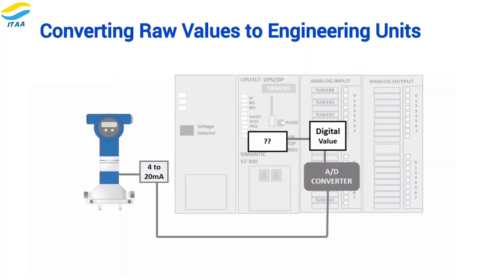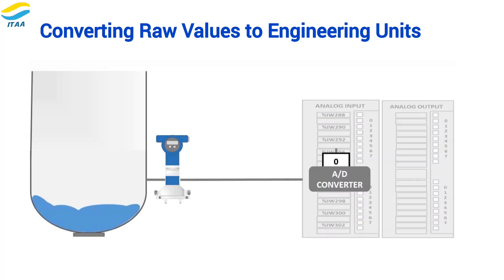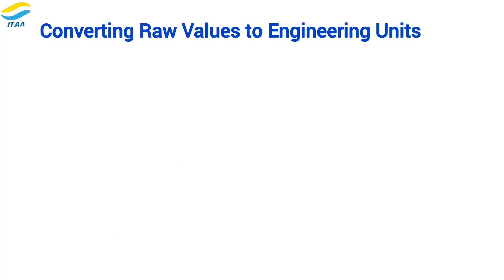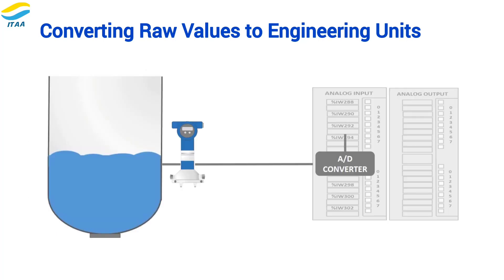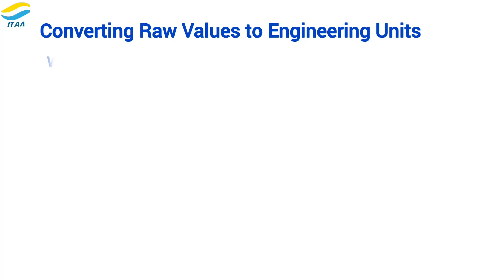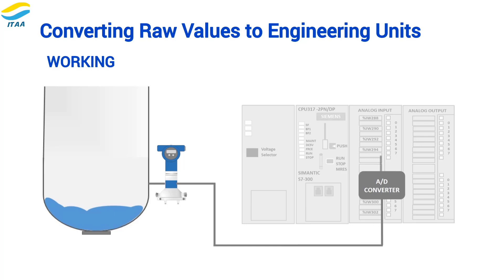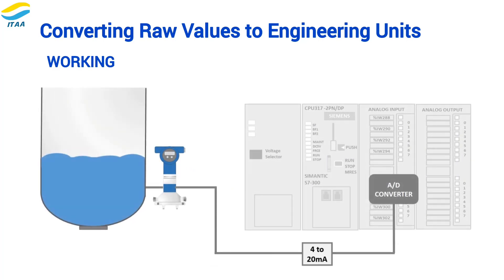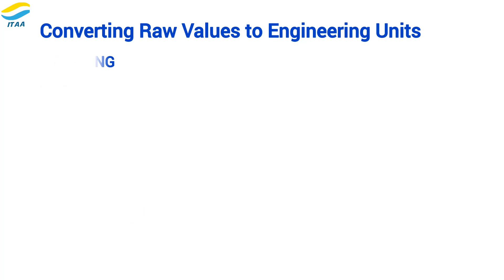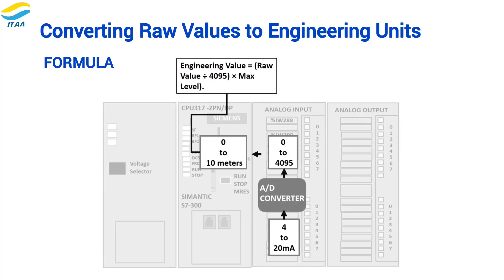The raw count itself doesn't directly tell us the tank level in meters — it's just a number. To make it meaningful, the PLC scales this raw count into an engineering value, like meters, that we can actually use in our control logic. If the raw count is 0, the PLC interprets the level as 0 meters. If the raw count is 4095, the PLC knows the tank is at its maximum level, let's say 10 meters. With a simple formula, the PLC converts any raw value from 0 to 4095 into a level measurement, so we can read the exact tank level in meters rather than just seeing a raw number.